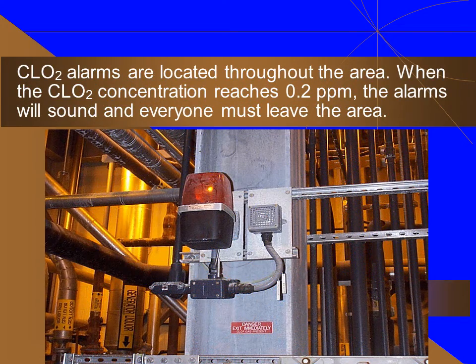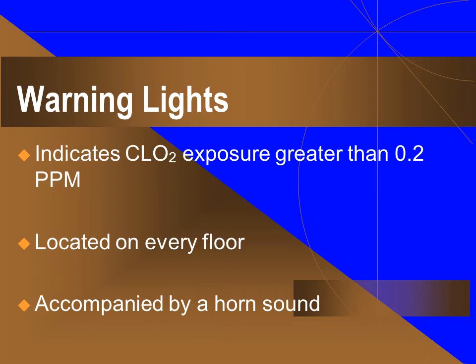Chlorine dioxide alarms are located throughout the area. When the chlorine dioxide concentration reaches 0.2 ppm, the alarms will sound and everyone must leave the area. Warning lights are installed as another indication of the presence of chlorine dioxide. The lights indicate chlorine dioxide exposure greater than 0.2 ppm. They are located on every floor and are accompanied by a horn sound.